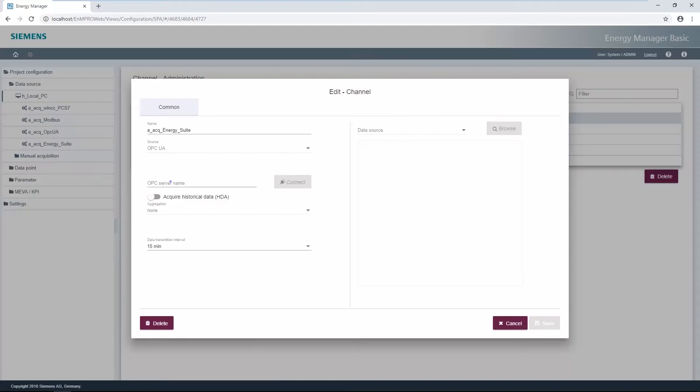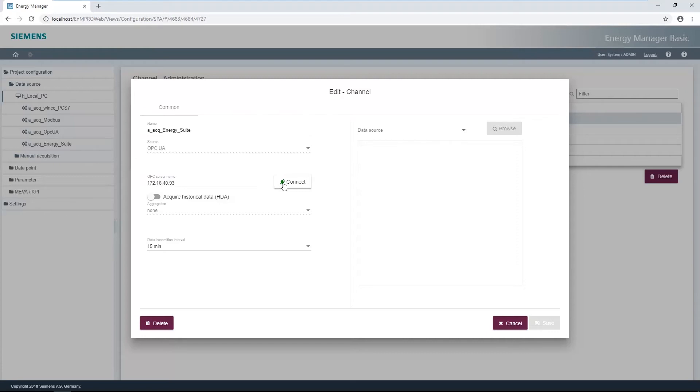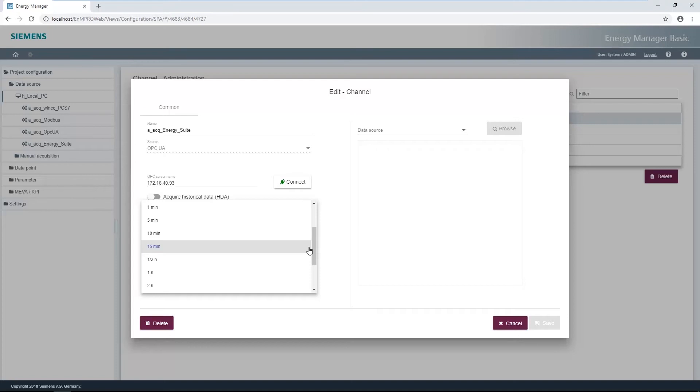Enter the IP address or computer name on which the WinCC OPC server is located. The button Connect determines all available OPC UA servers. The data transfer interval can be selected via a drop-down list. This interval also corresponds to the cycle time of the data point.